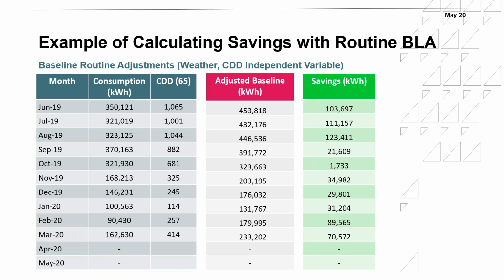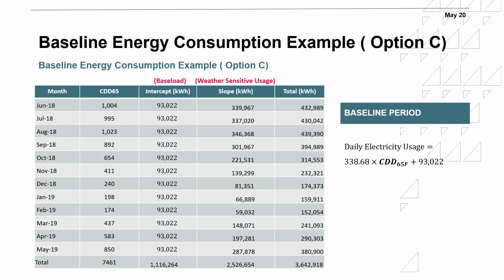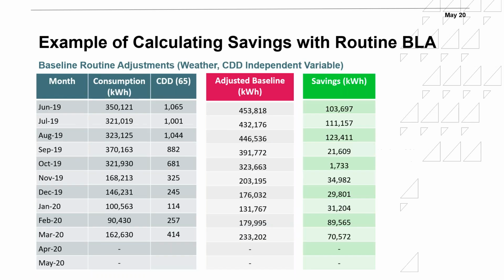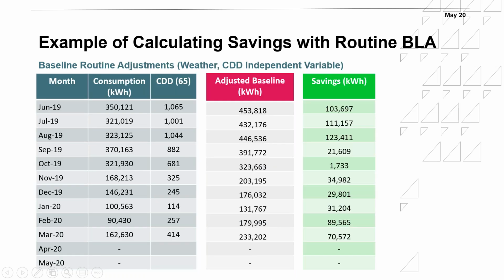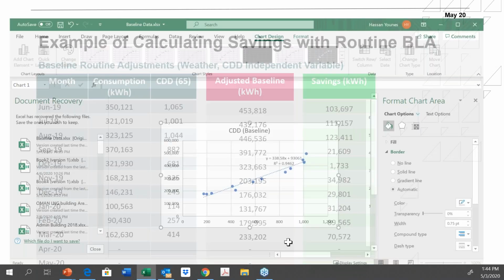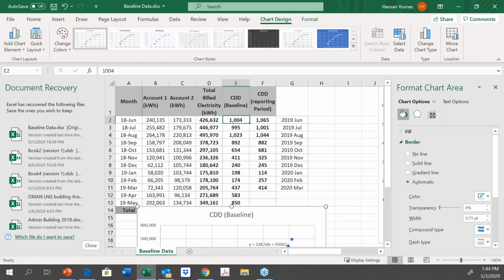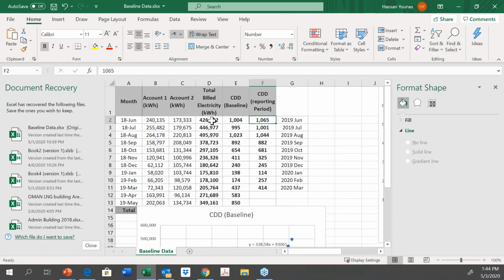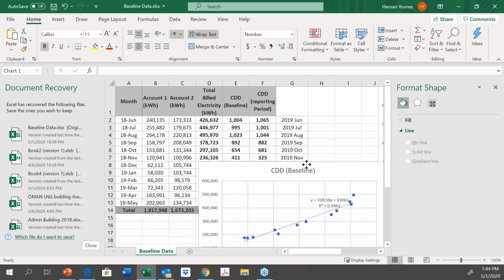So the cooling degree days for June 2019 is 1,065 compared to 1,004 in 2018. It means it got a little bit hotter in 2019, and that means I need to adjust the baseline, meaning that if the temperatures were the same as we are having them in June 2019, in June 2018, what would have been the consumption? So I need to adjust the baseline using that particular equation. So if I go to the Excel sheet, and I would use the new cooling degree days to derive the new consumption for the adjusted baseline.